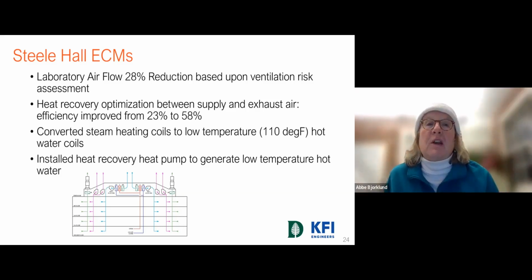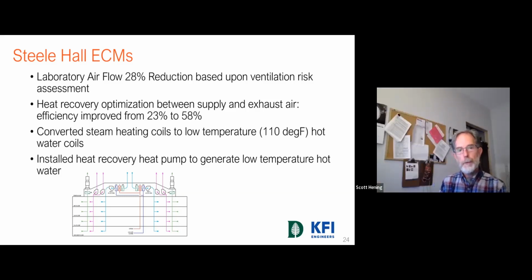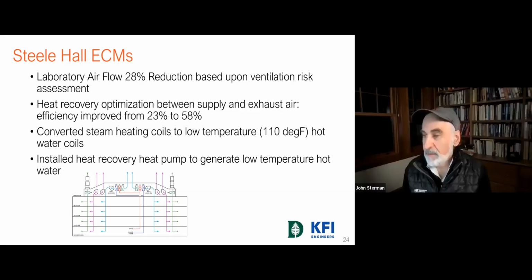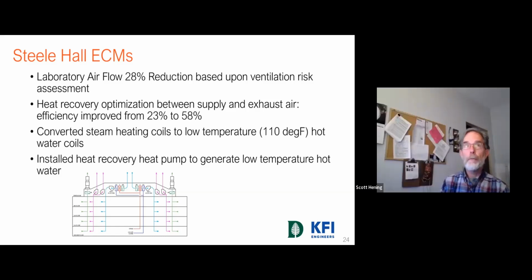Yeah, I think that was part of this 28% reduction, but I'll let Scott answer that question. We actually didn't have to do too much with the fume hoods. You already had variable volume hoods. The laboratory risk assessment basically found some locations where we could reduce the air changes per hour safely. On the third floor, there are some teaching labs with a really poor setup, a whole bank of hoods connected to one VAV. We were able to give the professor an occupied/unoccupied switch, so we can really cut back the airflow there, and they've been good at using it when they're not in there.